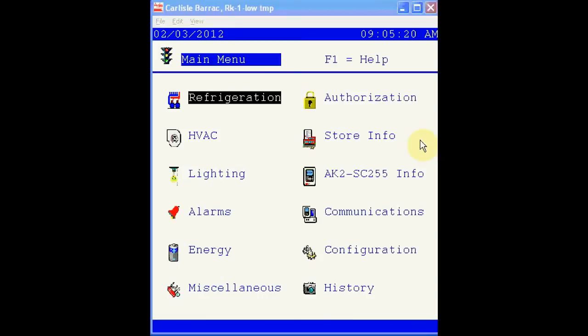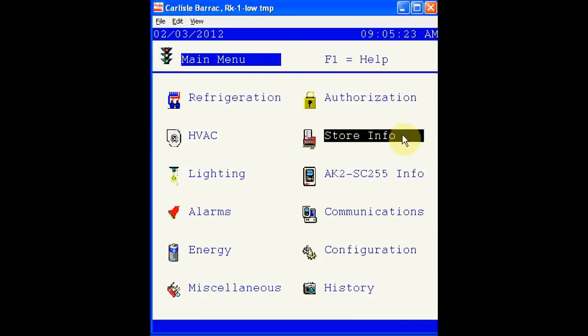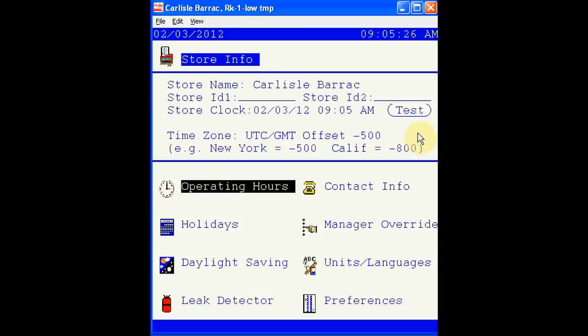Several general items are available in the Store Info screen, such as store name, the clock for this unit, operating hours, which are store hours, any holiday schedules, daylight savings dates, which can be changed, but should be left at factory defaults, any leak detector setups, notes about contact info, manager's override, which typically will override lighting loads, and options to change units for measure, languages, and other preferences.